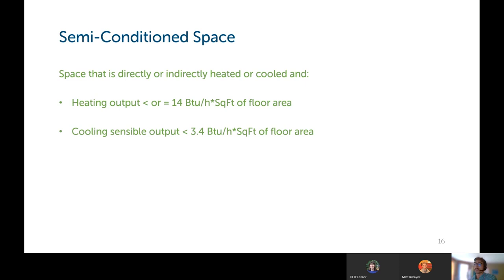A semi-conditioned space is new for this version of the code. So this is a space within a building that is directly or indirectly heated and cooled, and has a heating output of less than or equal to 14 BTU per hour per square foot of floor area, and would have a cooling sensible output of less than 3.4 BTU per hour per square foot of floor area. And my thought is that warehouses and storage areas that are either not cooled and/or not heated to very high temperatures may fall into this category. And I will show where this comes into play later on, typically for the building envelope.